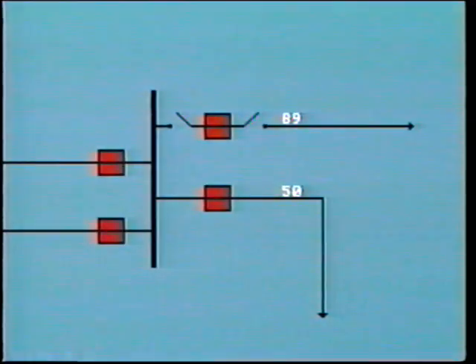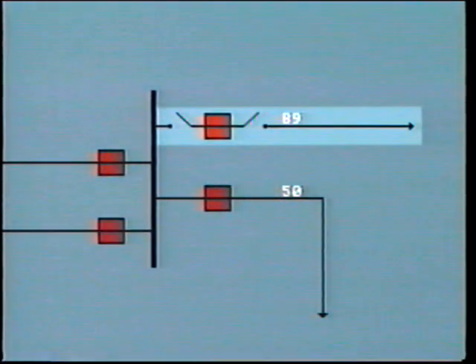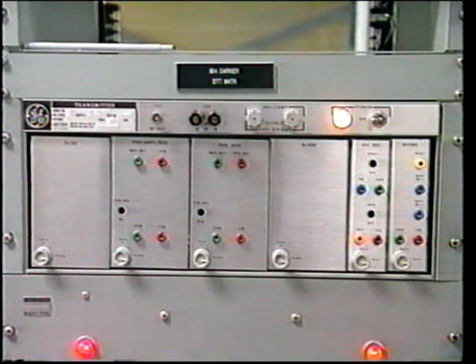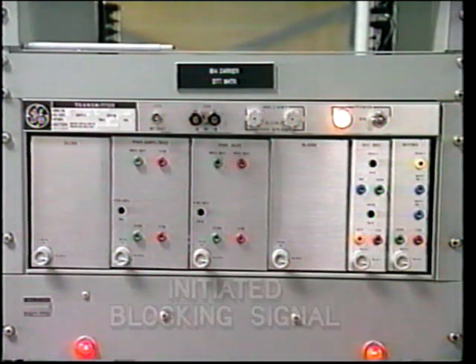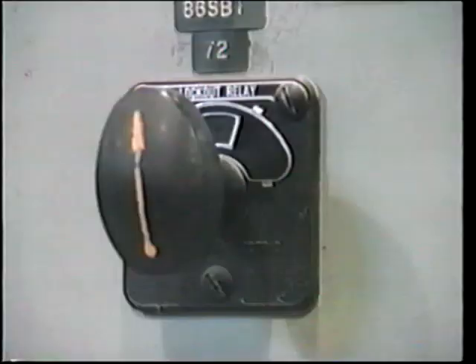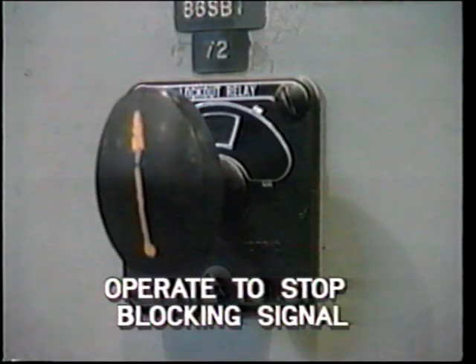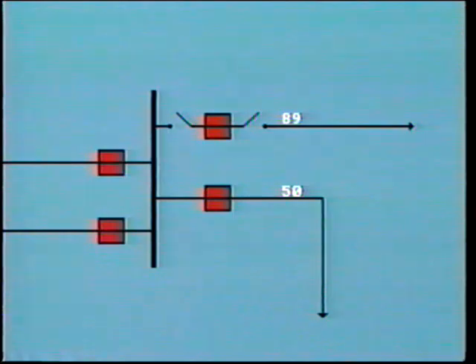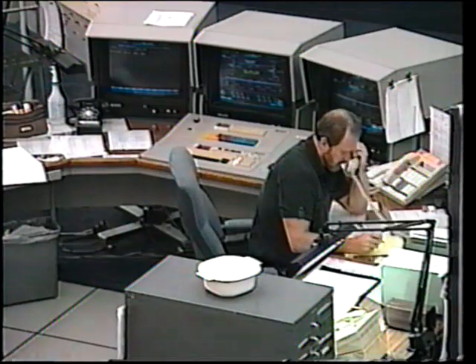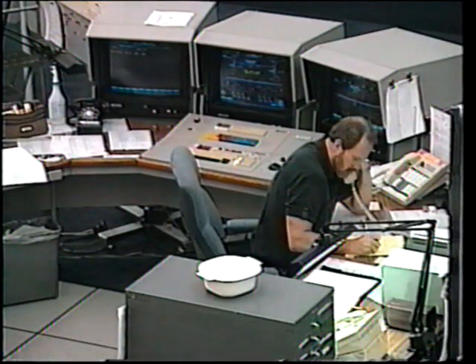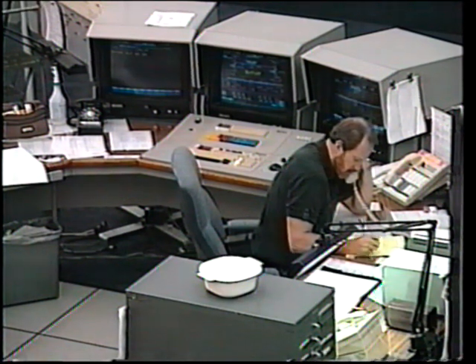The two technicians were performing tests on this isolated feeder number 89. They had a permit to work and were proceeding to test the carrier and associated equipment. One technician located at the carrier equipment panel initiated a blocking signal and signaled to his companion at the relay panel to operate the lockout relay so as to stop the blocking signal. However, in order to improve communication between them, this fellow moved his position just slightly, but enough to cause him to operate the relay on the adjacent panel. As a result, feeder number 50 tripped. Realizing what they had done, the technicians immediately informed the operator, and the feeder was restored within minutes.